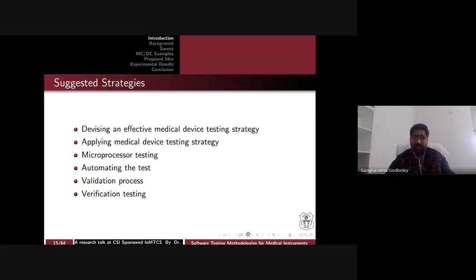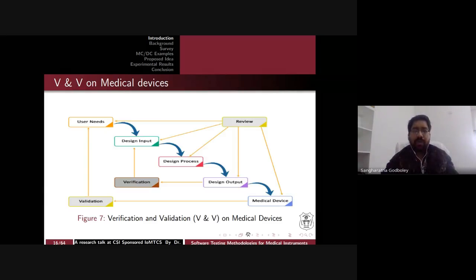So applying medical device testing strategies, microprocessor testing, of course, because devices are there, and it's not only software testing that is required, they require hardware testing as well. So microprocessor testing must be based on that. But that microcontroller software, that assembly code, definitely must get tested before the actual device is tested, right? So automating the test and validation process and verification test. Okay. So this is what V and V for medical devices means, the verification and validation model for medical devices.